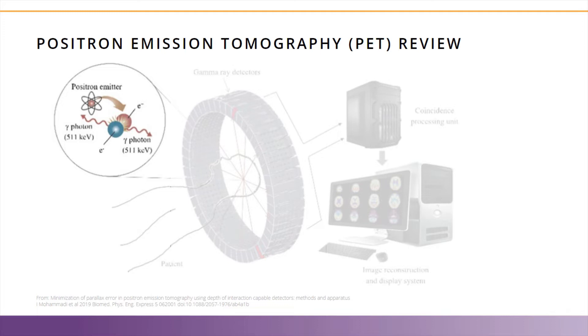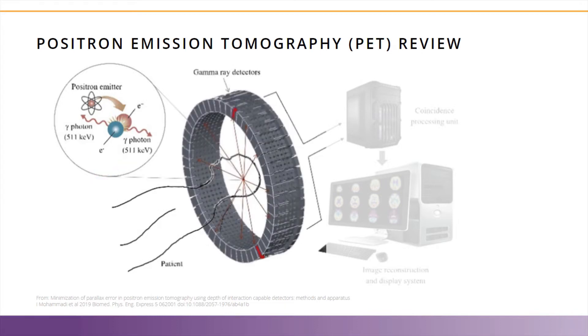In the case of tumor detection, a radioactive isotope of glucose is used, called FDG, or fluorodeoxyglucose, and it has an F18 radioactive atom included in its structure. This radioactive tracer accumulates in areas where there is high metabolic activity, including tumors. As F18 and other radioisotopes decay, they emit a positron, which then travels a short distance and collides with an electron in the surrounding tissue. This interaction causes an annihilation event, resulting in the release of two gamma photons in approximately opposing directions, which travel until they encounter the gamma ray detectors.